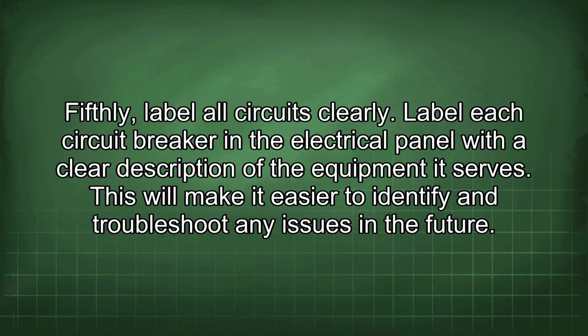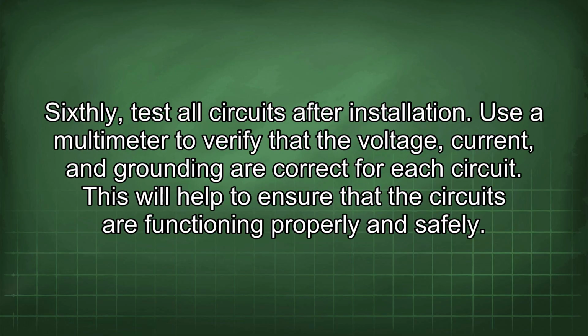Fifthly, label all circuits clearly. Label each circuit breaker in the electrical panel with a clear description of the equipment it serves. This will make it easier to identify and troubleshoot any issues in the future. Sixthly, test all circuits after installation. Use a multimeter to verify that the voltage, current, and grounding are correct for each circuit. This will help to ensure that the circuits are functioning properly and safely.